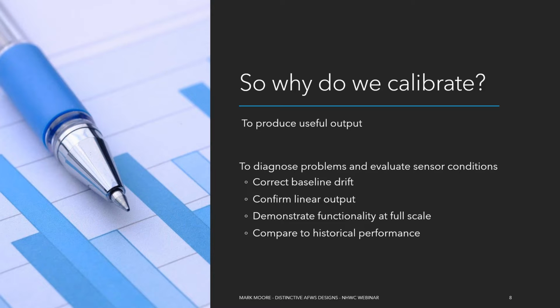So why do we calibrate? Primarily, it's to produce a useful output so that our flood warning systems are actually sending data, because you can't put on your public facing website that the water level rose 0.197 psi. People aren't going to know what that means. What we want to say is that the water level rose 2 feet. But there's other advantages to calibration as well. They can help correct baseline drift. It helps confirm that you have a linear output, which we'll talk about in a little bit.